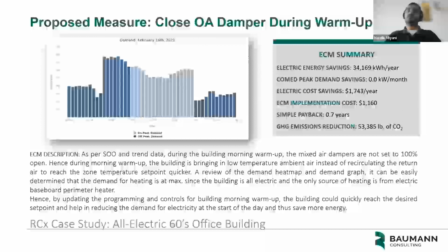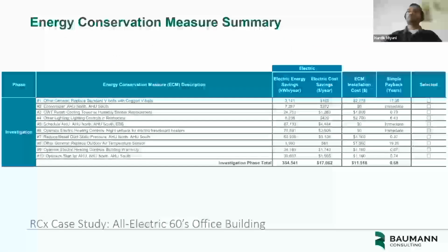By upgrading the sequence of operation, by closing the OA damper during the building warm-up time, the building will be able to save almost 34,000 kilowatt hours of energy annually. Since there will be a programming update needed as part of this ECM, we reached out to the controls contractor, and he provided us with a costing of almost $1,100 for this ECM.